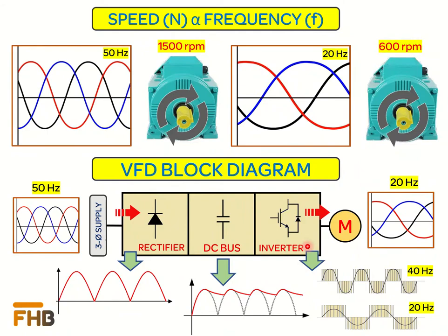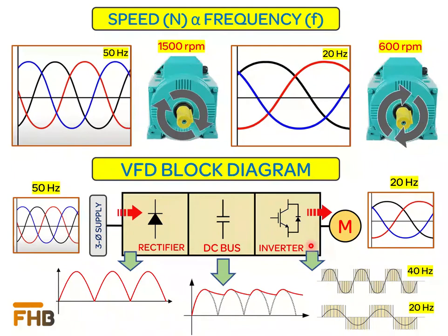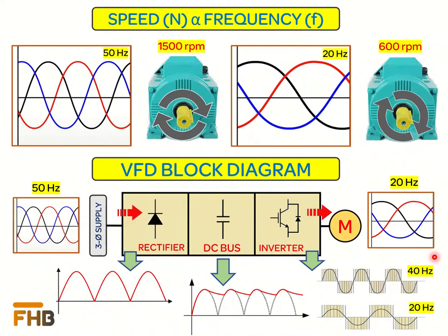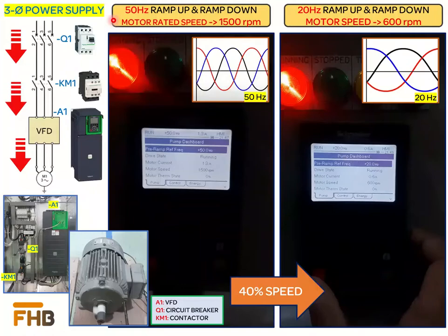In the third stage, called the inverter, switching action using electronic switches such as IGBTs converts the DC output from the DC bus into a rectangular waveform that reflects the shape of a sinusoidal wave. The frequency of the output waveform is controlled by regulating the switching frequency of the IGBT switches.